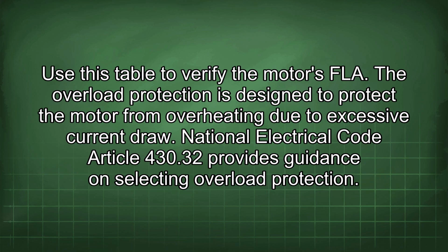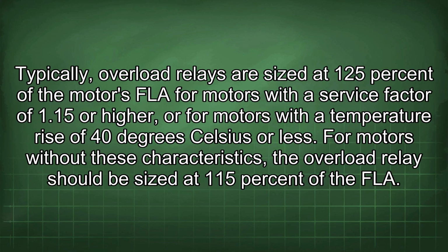The overload protection is designed to protect the motor from overheating due to excessive current draw. National Electrical Code Article 430.32 provides guidance on selecting overload protection. Typically, overload relays are sized at 125% of the motor's FLA for motors with a service factor of 1.15 or higher, or for motors with a temperature rise of 40 degrees Celsius or less. For motors without these characteristics, the overload relay should be sized at 115% of the FLA.